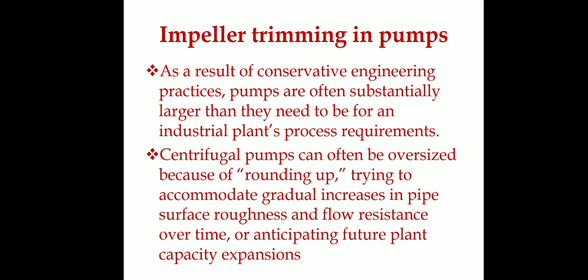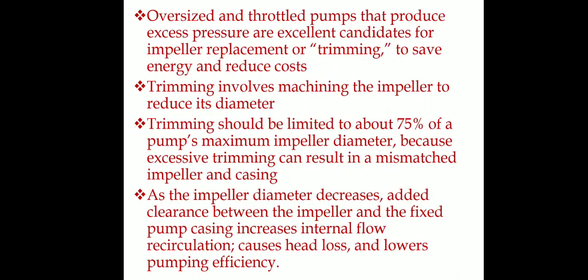Normally, when we are doing this selection, we require the impeller to match the current situation. However, if we select an oversized impeller for the current situation, the efficiency will reduce rapidly. That is why we have to trim the diameter of the impeller.